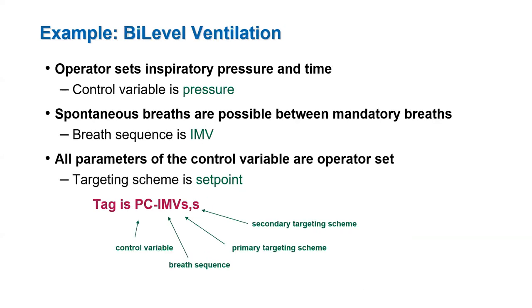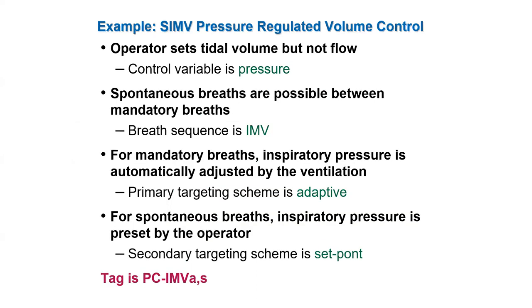Here's another example for the mode called bi-level ventilation. In this case, the breath sequence is IMV, for which we have both mandatory and spontaneous breaths. For that reason, we need at least two abbreviations for the targeting schemes. Thus, the first S represents set point targeting for mandatory breaths, and the second S represents set point targeting for spontaneous breaths. Here's another IMV mode, but this time with adaptive targeting for mandatory breaths and set point targeting for spontaneous breaths.